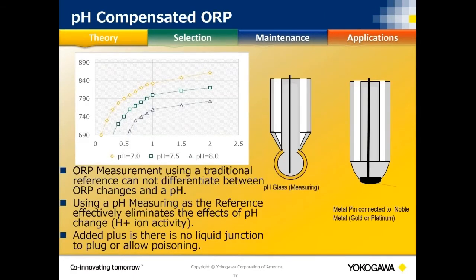There is also a solution ground to ensure stable reference voltage, because the path of least resistance is through the reference electrode. Any stray noise will go through your reference and give errors in your reading. If you have a solution ground and the whole process is grounded, you eliminate the possibility of grounding or noise interference.